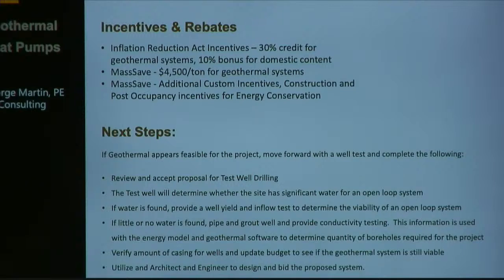Next steps: we really would like to promote a proposal for a test well, which involves drilling a well, looking at how much overburden you have, checking if there's water, and doing a conductivity test. This allows us to put that data into our energy model to fine-tune the borehole field so we're not over-designing something. Geothermal does have a cost, so we don't want to add boreholes just for the sake of adding boreholes. We need to tune this thing up.